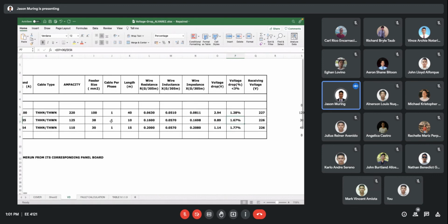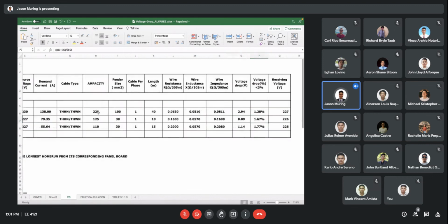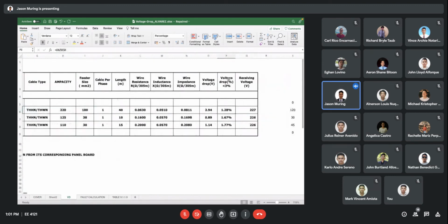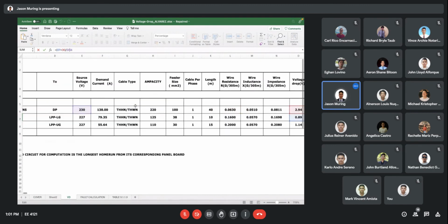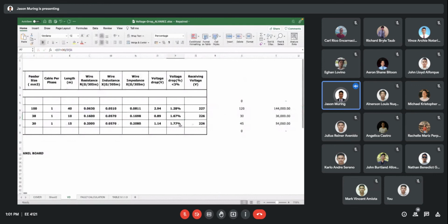Even if there are some things they probably did not consider here, because they are using this, instead of just considering the branch circuit alone, they also consider the effect of voltage drop in the panel or feeder circuit. In our case, we can just use the per branch circuit calculation.